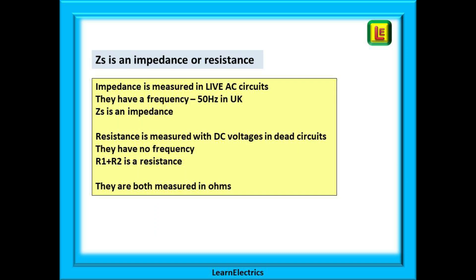First let's clear up one little thing. ZS is an impedance because it is measured on a live circuit — alternating current — it has frequency. Resistance is measured on DC circuits with no frequency. R1 plus R2, for example, is a resistance, a DC measurement on a dead circuit. But they are both measured in ohms, and at 50 cycles per second (50 Hertz) the difference between impedance and resistance is so very small that it is not worth worrying about. So for me, if you call ZS a resistance or you call it an impedance, I would still know what you were talking about.